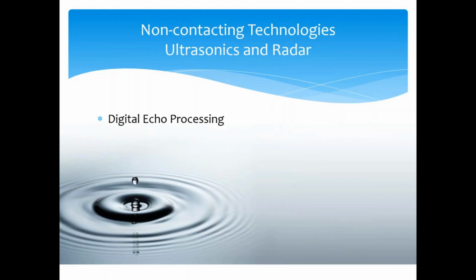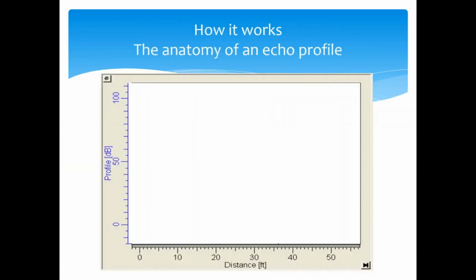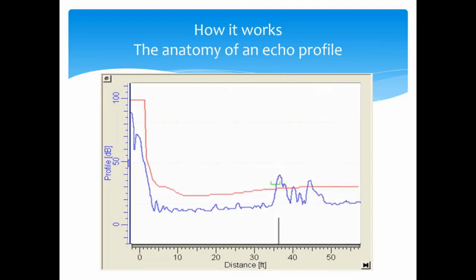All right, so now we're going to talk a little bit about the digital echo processing between these two technologies, and they work very, very similarly. So this is what's going on in the background of either of these non-contact technologies while they're making the measurements for you. So what you're going to see here is a little chart. Along the y-axis, I have decibels, which is basically the sound or the noise in the application, which we'll talk about in a moment. Along the x-axis, I have my distance. On the left-hand side, I'm going to start at 0 distance from the transducer, and as I continue along, that'll be the depth of my tank or my vessel.